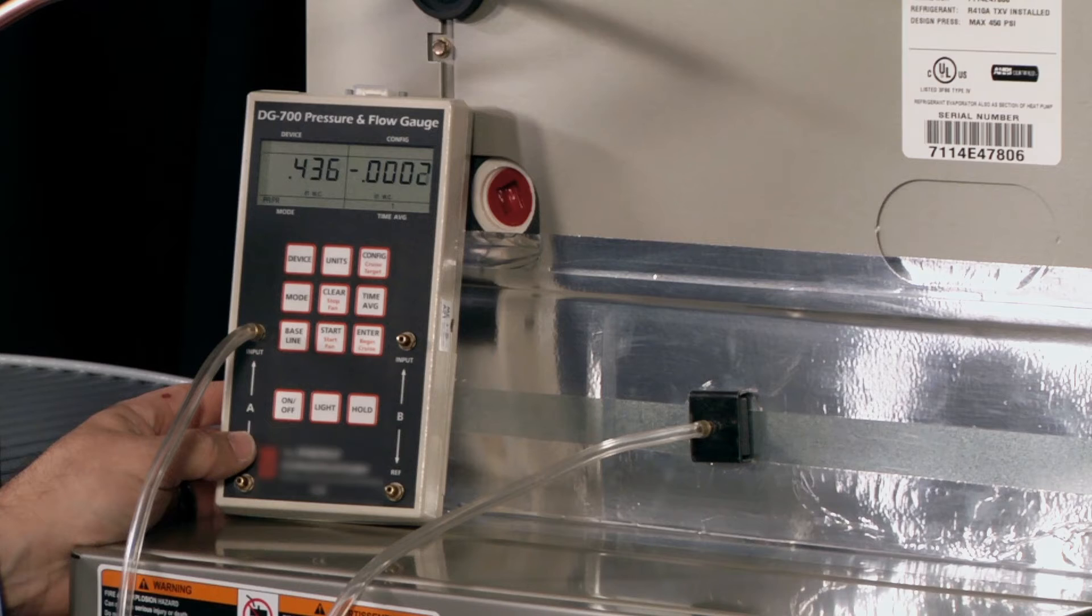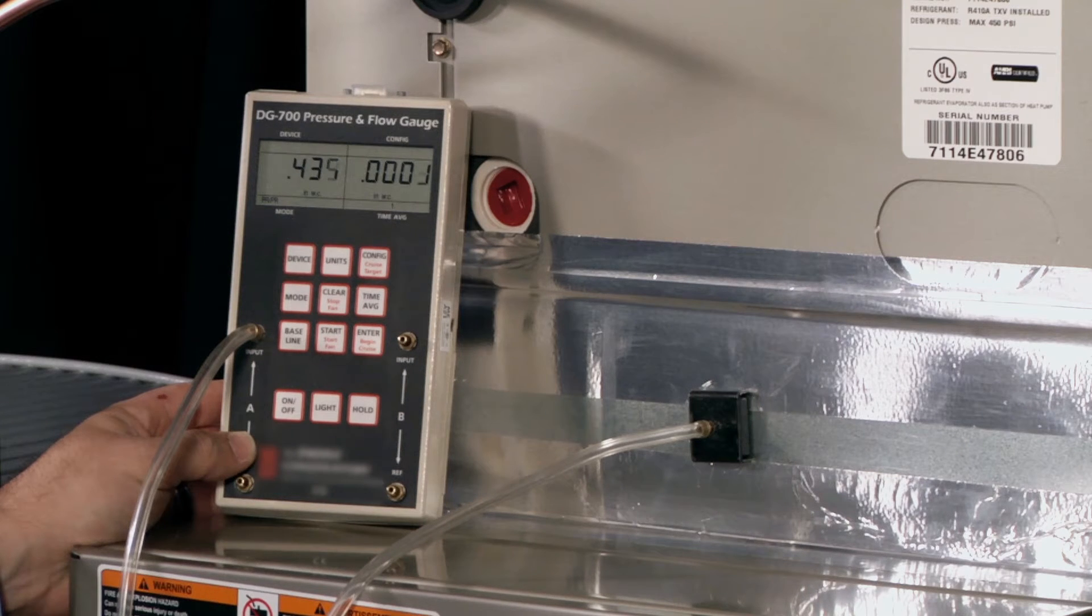He's going to position the probe so that it's pointing in the direction of the airflow, this way. Here we see the readout from the manometer. He gets a value slightly higher than 0.4 inches water column.